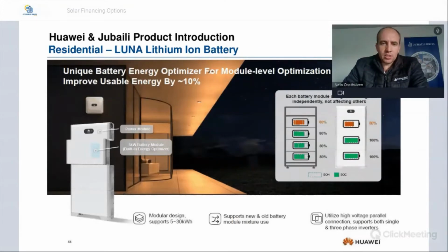Then, as I've mentioned, it supports new and old battery module mixed use. So you can start off with just a single battery or 2 batteries. Then after a few years, you can add more batteries, and the newer batteries will not be affected by the older batteries. Then also important to note is that the Huawei batteries are high voltage batteries. They operate in the range of 480 volts DC to 600 volts DC. So you can have a reduced cable size when connecting up the batteries.